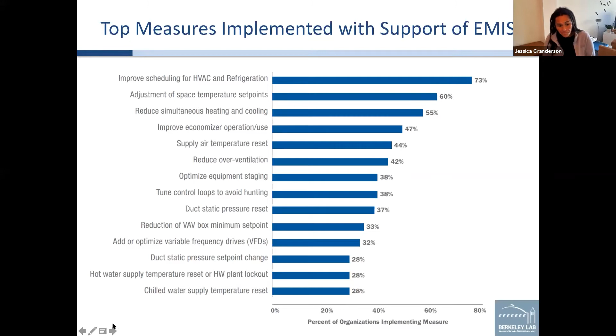A variety of measures are all around reset strategies, whether that's duct static pressure, supply air temperature, or chilled water and hot water reset points at the central plant level. And then there's also a class of savings all around just ensuring that set points are appropriate and not overly aggressive for the needs of the spaces being conditioned.